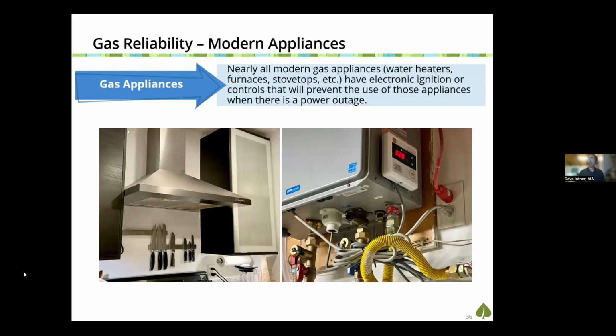Nearly all modern gas appliances require electricity to operate. Your furnace won't blow air through the house if the fan blower motor doesn't have power. Cooking shouldn't be done without proper ventilation and your range hood working, any more than you'd roll a propane grill into your kitchen and cook on that. Similarly, stoves, furnaces, and water heaters generally require electronic ignition and/or power exhaust, all of which require electricity. So in an outage, arguably a tank-type heat pump water heater provides more resilience, because you have 50, 60, 80 gallons of hot water sitting there you can draw off of even if the power's out.